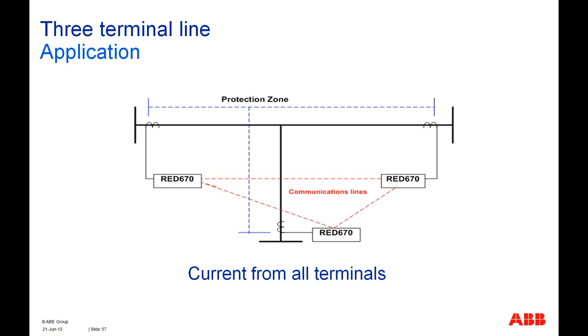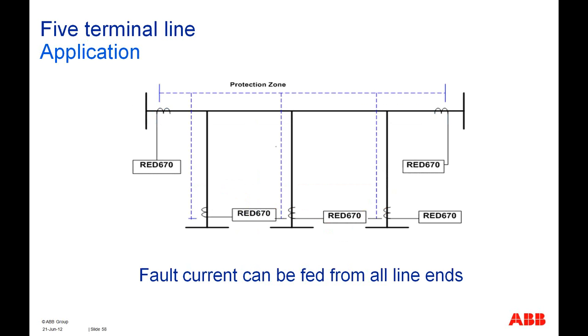In the case of three terminal lines, we will have one box at each station. So we will have three RED 670 boxes, connected with the transmission communication lines. And the currents from all the terminals will be calculated and transmitted to the others for the calculation of the differential as well as stabilization quantities. In case of 5 terminal lines, we will have 5 boxes, and each box is connected to the others, and the decision is made depending upon the topology of the communication network.